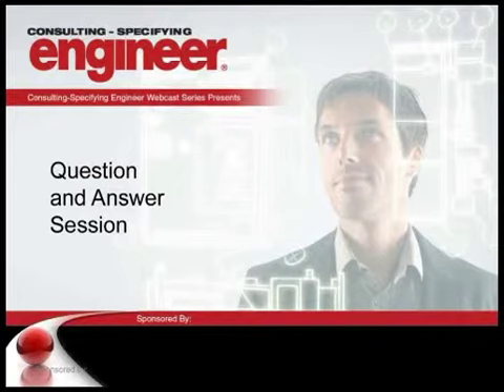Dean, question for you from Paul Luoma from Reston, Virginia, asking: when using a make before break ATS, do the generator and utility contributions need to be added to determine the fault current? That's a good question. In many cases, that's an ambiguous question. I think the best answer is probably to ask your authority having jurisdiction. I've seen cases where you can not account for it, and I've seen cases where you are forced to account for it.